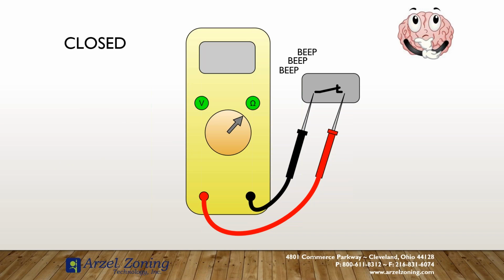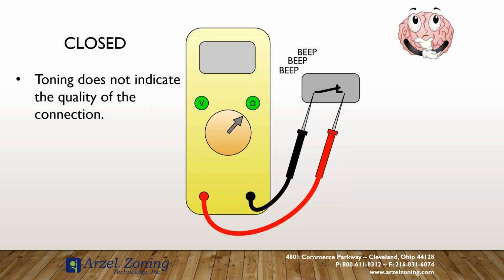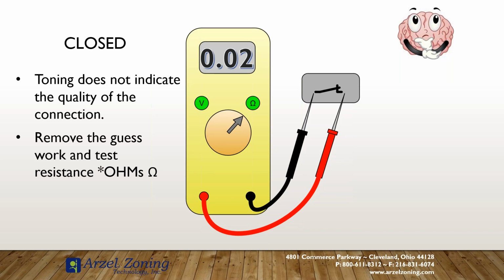If I have a closed set of contacts, a lot of technicians listen for that beep, beep, beep on their meter, but that toning doesn't indicate the quality of contacts. So if I'm going to ohm it out, what am I looking for to say that that's a good set of contacts? Zero would be perfect. However, in an imperfect industry, we're actually looking for anything less than 1 ohm of resistance. So if it's less than 1 ohm of resistance, we know that there's not significant impedance. The closest I have ever seen to zero is a 0.02, and that's essentially just touching my meter probes together. So there is some resistance to our meters themselves, not significant. There is some resistance to everything. However, we're looking for less than 1 ohm of resistance, and that indicates that we have a good contact.